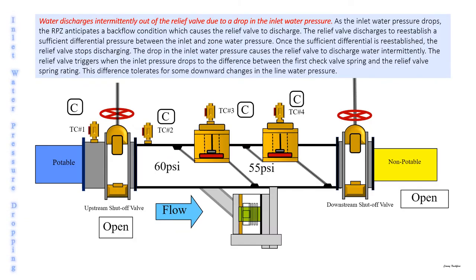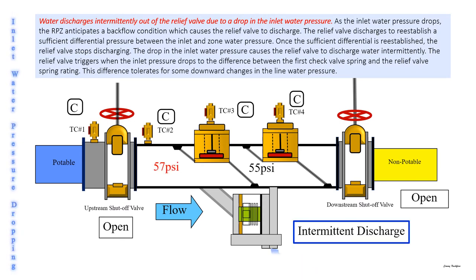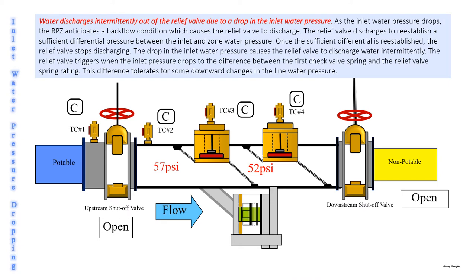Water discharges intermittently out of the relief valve due to a drop in the inlet water pressure. As the inlet water pressure drops, the RPZ anticipates a backflow condition which causes the relief valve to discharge. The relief valve discharges to re-establish a differential pressure between the inlet and zone water pressure. Once the differential is re-established, the relief valve stops discharging. The relief valve triggers when the inlet water pressure drops to the difference between the first check valve spring and the relief valve spring rating. This difference tolerates some downward changes in the line water pressure.